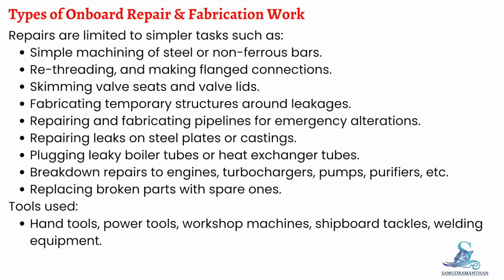The fabrication and repair work on board is usually limited to simple machining of steel or non-ferrous bars, rethreading, making flanged connections, skimming valves, seats and valve lids, repairing and fabricating pipelines, and building temporary structures around leakages. Engineers may also repair leaks on steel plates or castings, plug leaky boiler tubes or heat exchanger tubes, and carry out breakdown repairs to engines, turbochargers, pumps, and purifiers. Many of these repairs involve replacing broken parts with spare parts available on board.